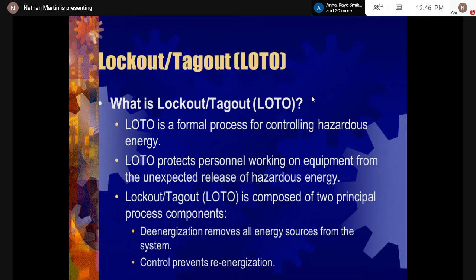So once you hear a person mention LOTO in terms of electrical, it is telling you about lockout and tag out. And we say this is basically the formal process for controlling hazardous energy. LOTO protects personnel working on equipment from the unexpected release of hazardous energy. It is composed of two principal process components. De-energization, that's removing all energy sources from the system. Control prevents re-energization. That's where the lockout comes in. So the lockout prevents re-energization, while the first part of the process is where you go and de-energize the circuit, then you will lock out, and then you will tag the system.